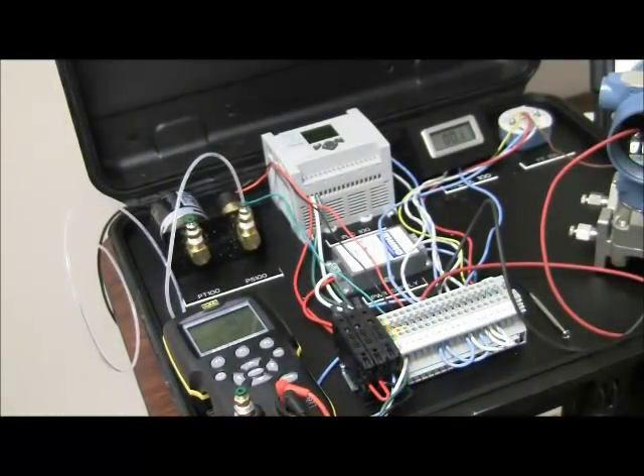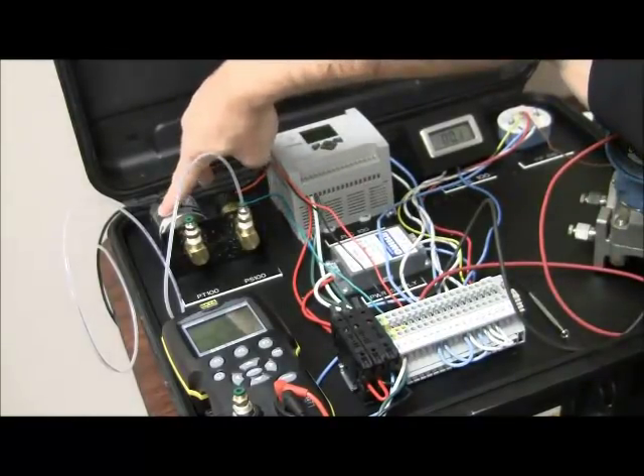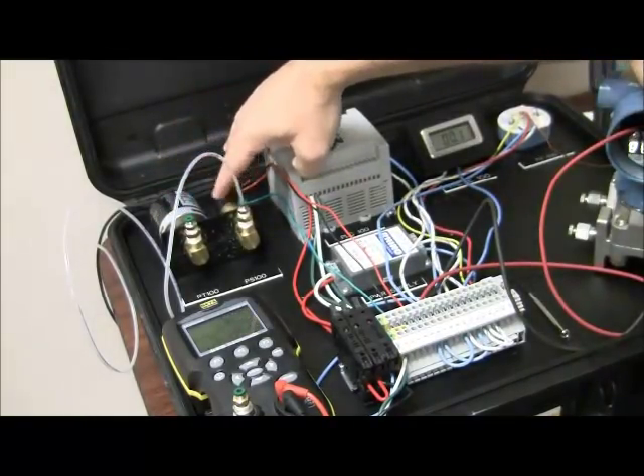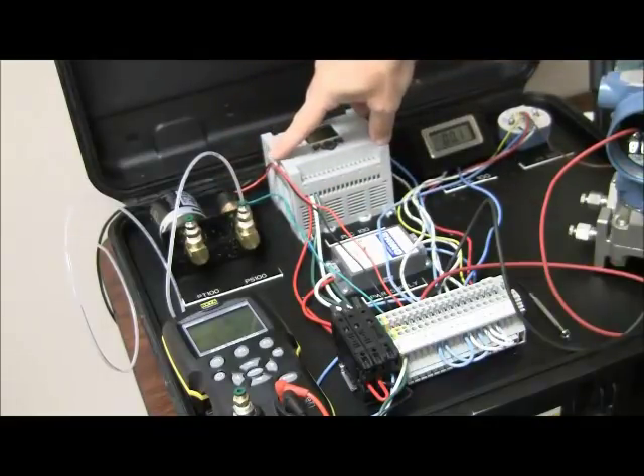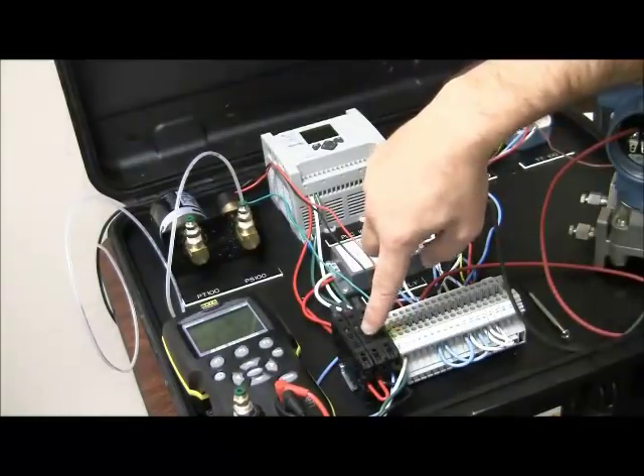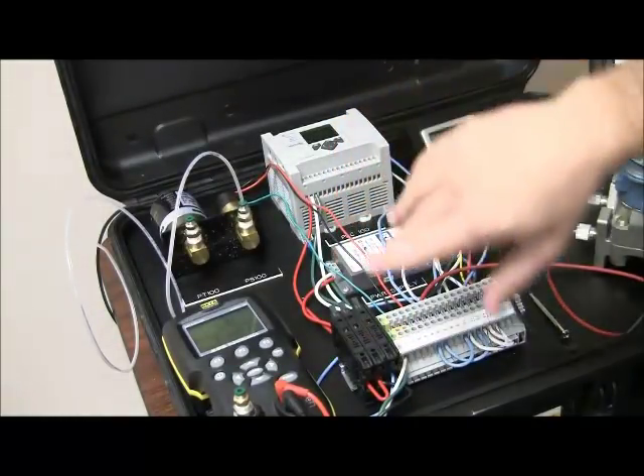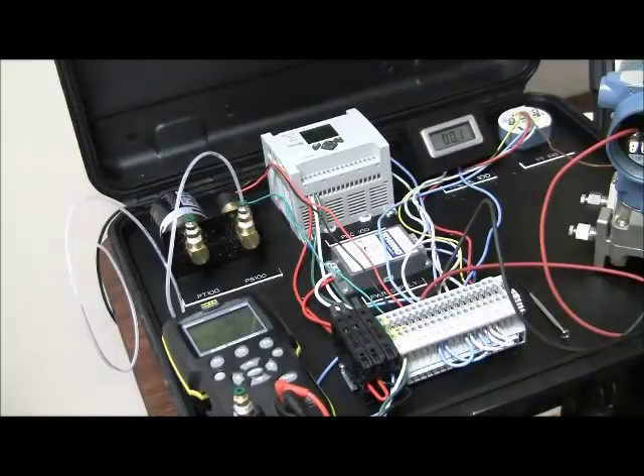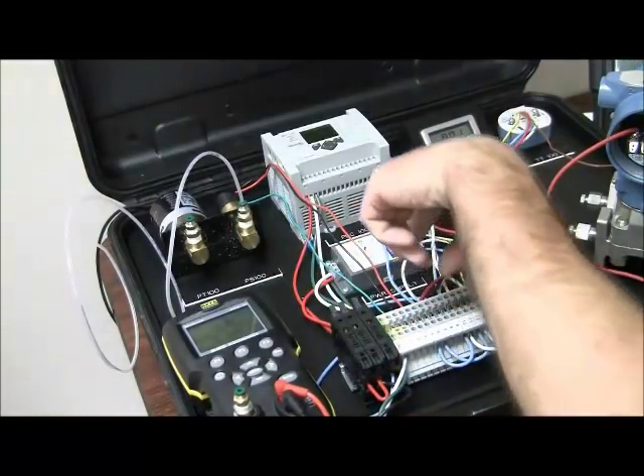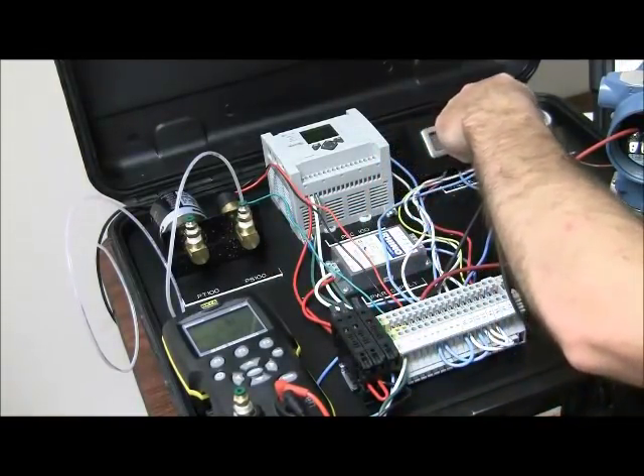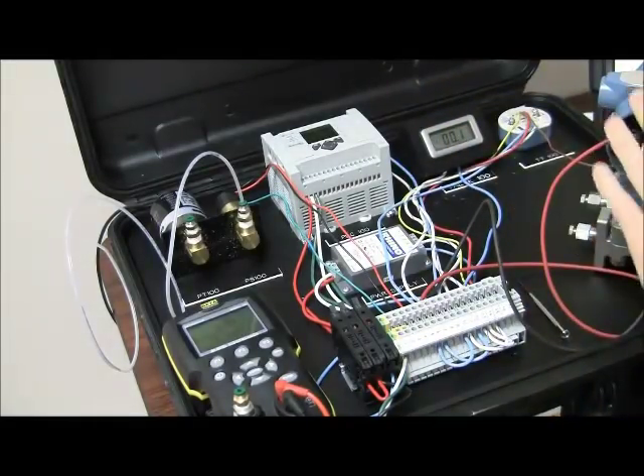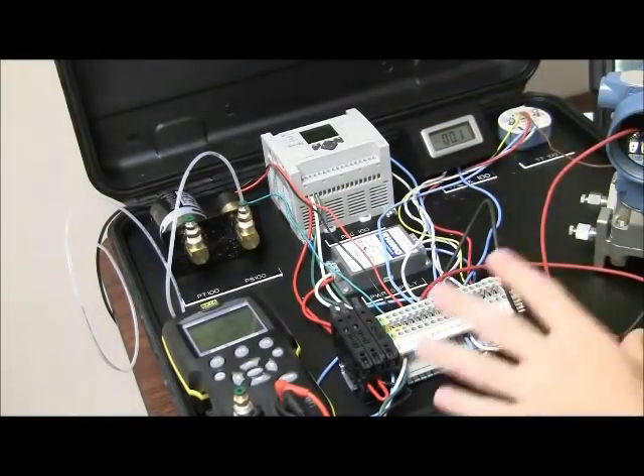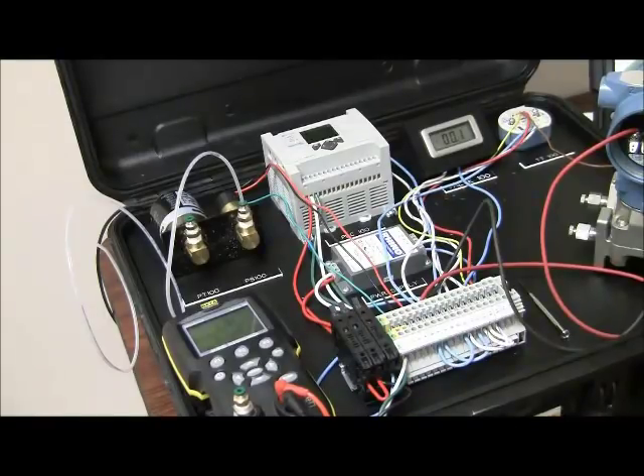So what I have here is a pressure transducer 100 psi, a pressure switch 100 psi, I have a PLC here, Allen-Bradley, I have AC coming in and a 24 volt DC supply here, a fuse block system here with terminal blocks, so the loop is powering up, my additional loop indicator, my transmitter, that's a temperature transmitter, my pressure transmitter. So I have a lot going on here, it's kind of a mini mock-up in a plant.